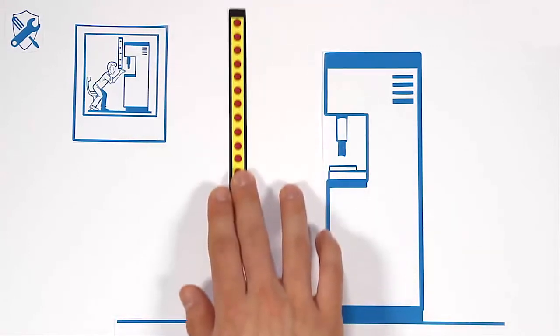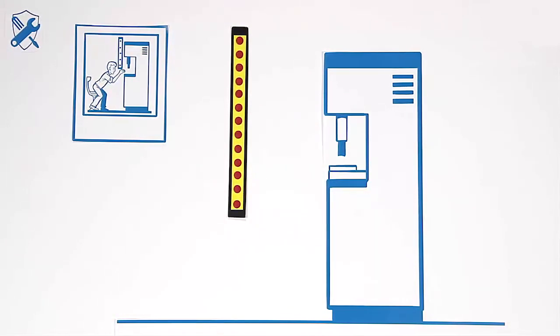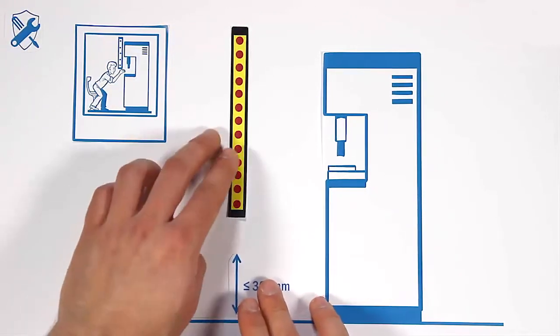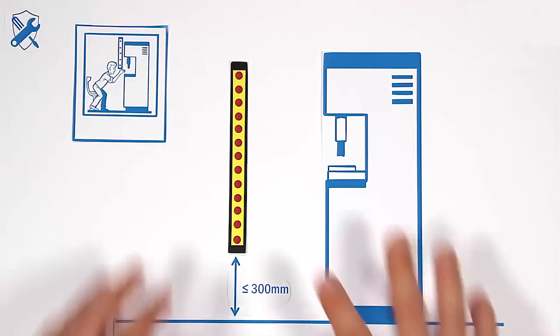In reaching under situations, crawling under the active optoelectronic protective devices has to be avoided. In case of access prevention, the maximum gap between the first beam and the floor shall be 300 mm max. Other distances from the floor underlie special requirements.